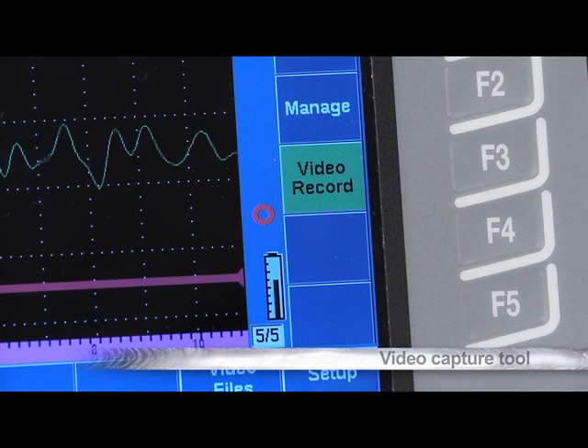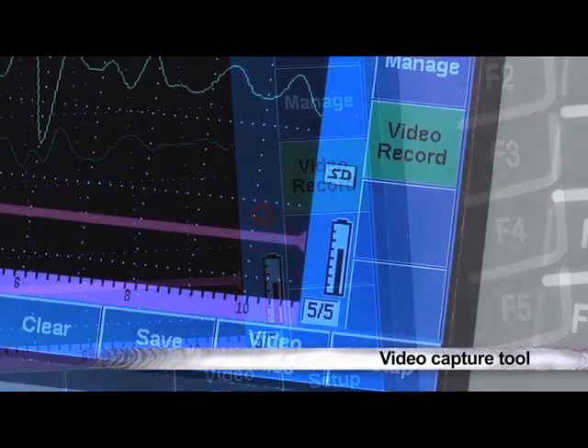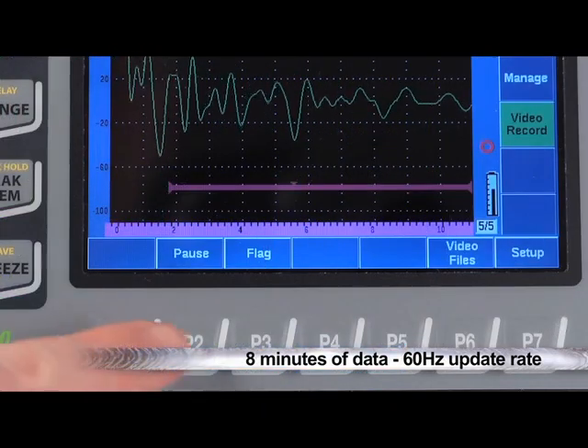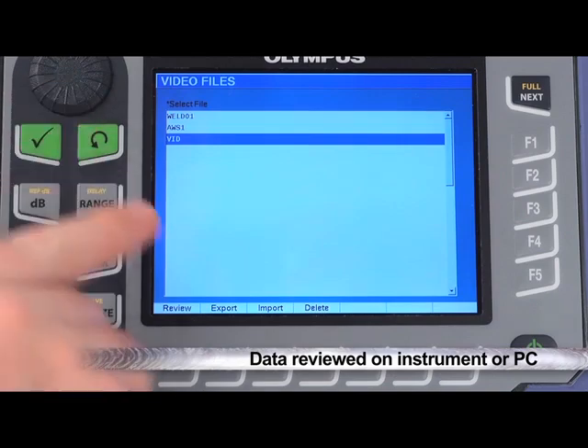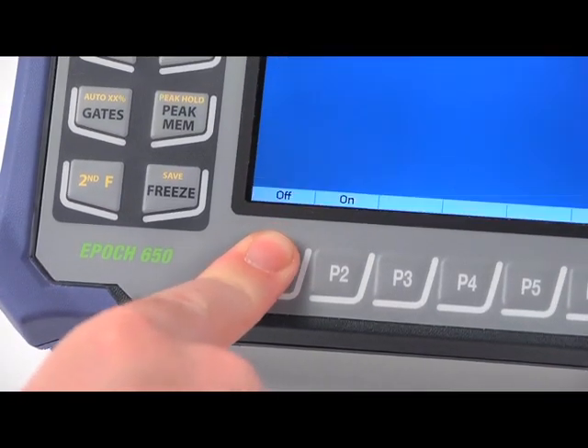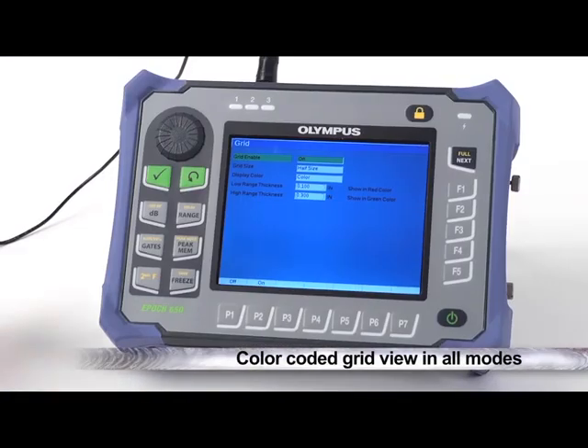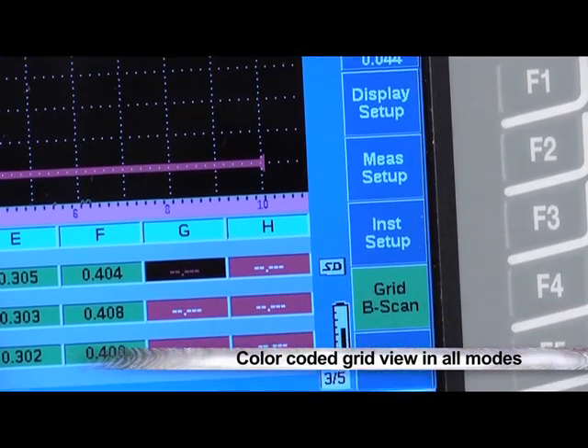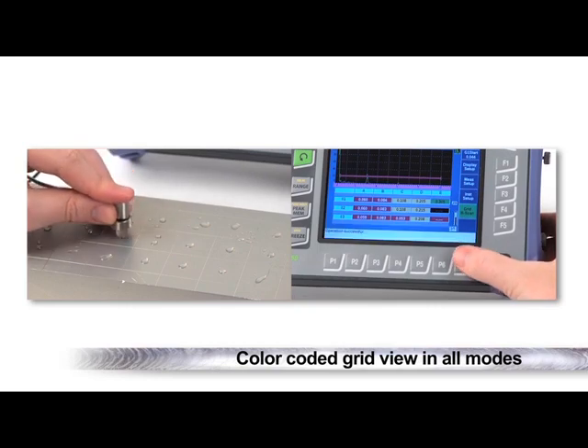To enhance static reporting capabilities, the EPOCH 650 comes standard with a video capture tool. This video record function collects up to eight minutes of data at a full-screen update rate of 60Hz. The data can be reviewed onboard the EPIC or quickly transferred to a PC for review and archiving. The EPOCH 650 also offers a standard color-coded grid view feature in all modes, which can be used for corrosion inspections or during single crystal inspections for quality control and other data collection surveys.